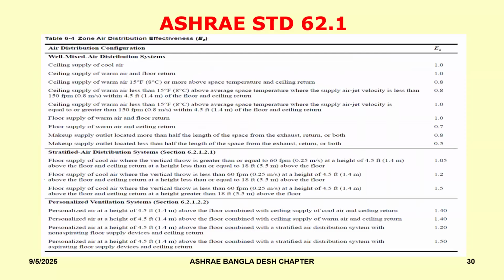You need to actually figure out, if I calculate some air quantity, let's say for a particular space, I say that based on the number of people and the area, we arrive at, say, 500 CFM. So how do I ensure that that 500 CFM of outdoor air, which I'm bringing into that space, is actually being distributed uniformly to all the occupants? Now, you can ensure that by making sure that the air distribution system that you have will be able to meet and comply with certain requirements. So there is something called air distribution effectiveness. Mind you, we're not talking efficiency yet. We're talking about effectiveness. So it gives you different types of air distribution systems that you could have.